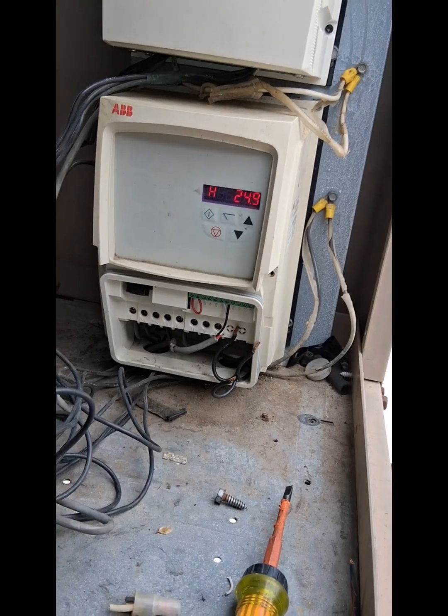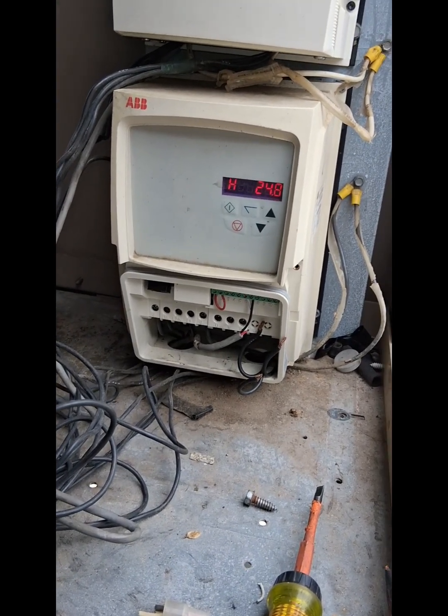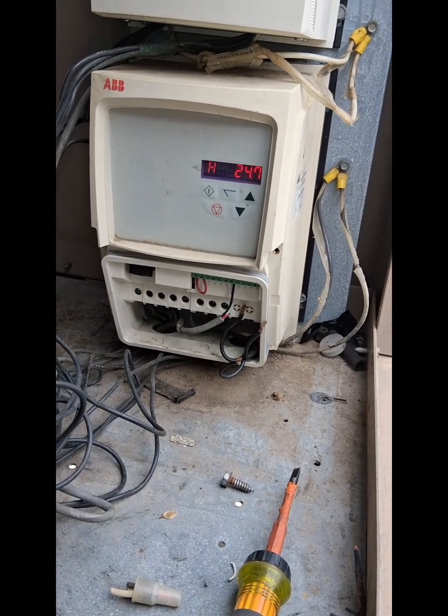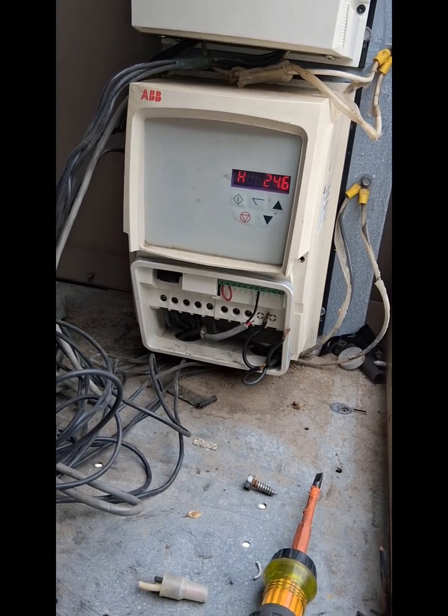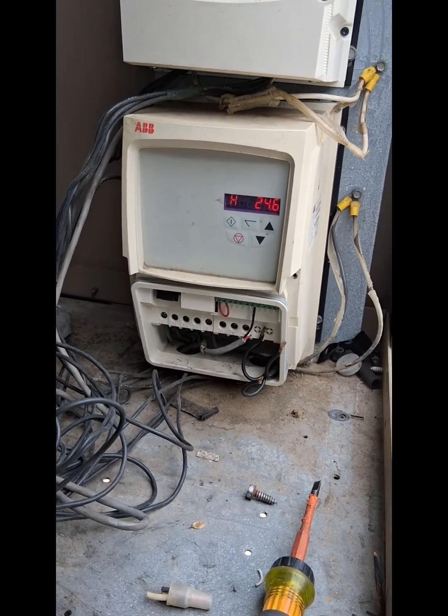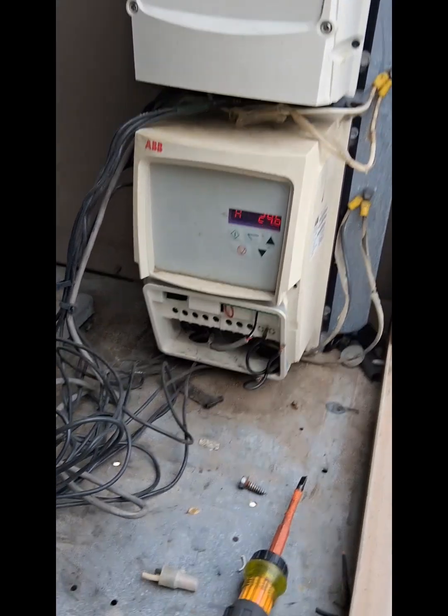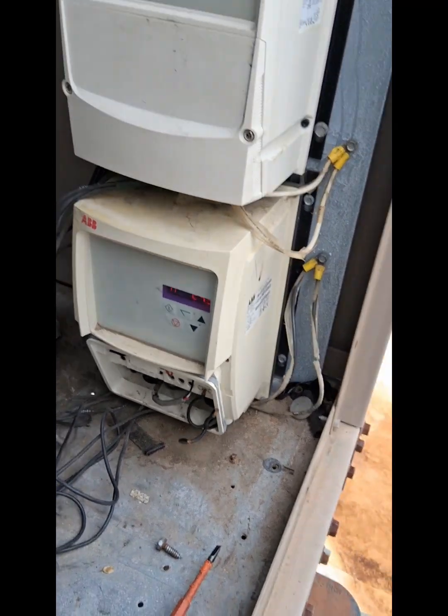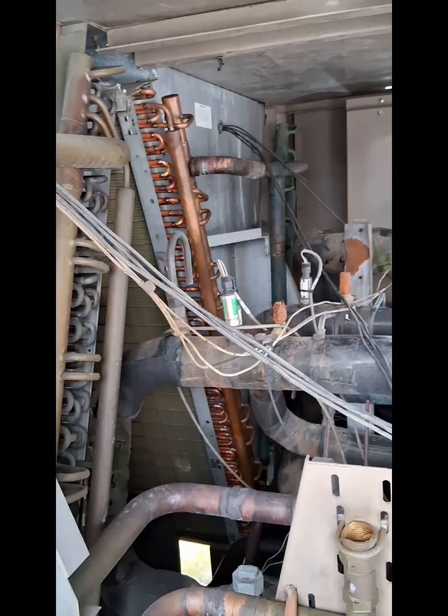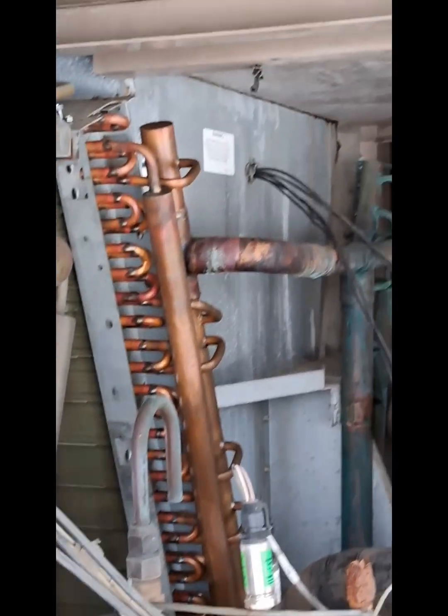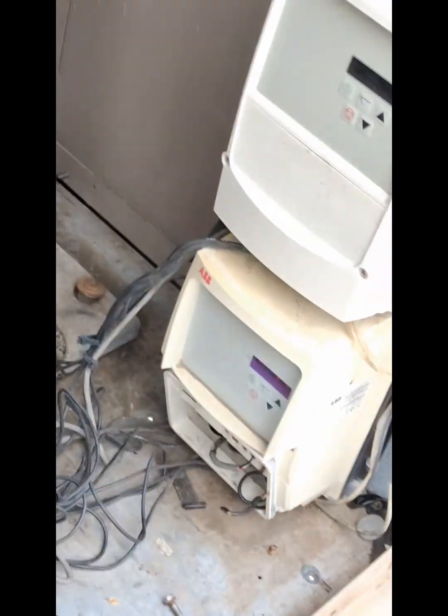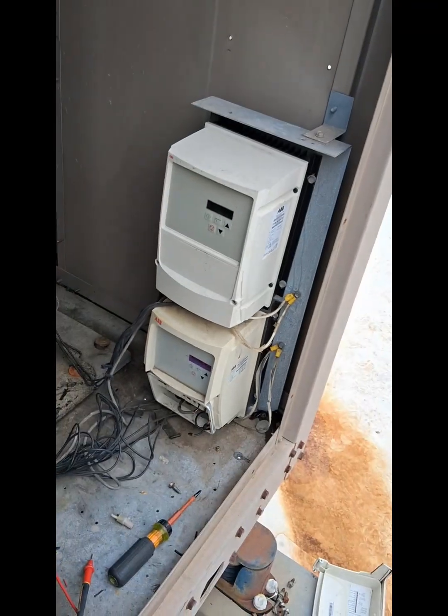The VFD ain't the problem. As soon as I unwired the load side going to the motor, the F001 alarm for overcurrent left. So it's something in that wire that's causing that drive to trip out. So I'm gonna look and see if I can find something rubbing out. Might be over there, or something rubbing out causing this drive to trip. So I'm gonna trace this wire down real quick and see if I can get the other fan up and going.